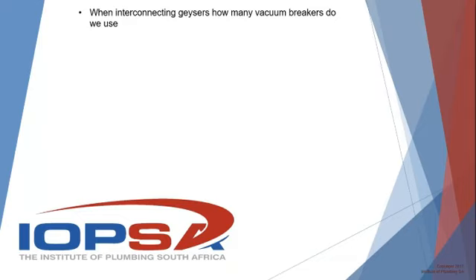Right. Okay. When interconnecting geysers, how many vacuum breakers do we use? So unless anybody wants to take this, I'm happy to say that, going back to 10254 and what constitutes a geyser installation, it's very clear that a geyser installation consists of certain things. And so, how long is a piece of string? How far apart are these geysers? And for safety's sake, we're going to include a hot vacuum breaker and a cold vacuum breaker for each geyser.